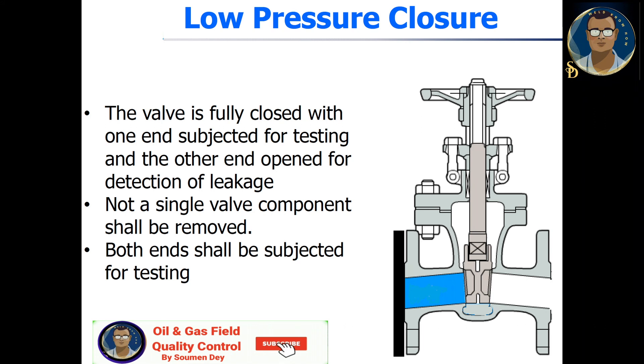Low pressure closure, or low pressure seat test: the valve is fully closed with one end subjected for testing and the other end open for detection of leakage. Not a single valve component shall be removed, and both ends shall be subjected for testing. As you can see in the picture, a seat is closed and water or hydro test fluid is filled — shown in blue — and from the other side we check if there is any leakage.